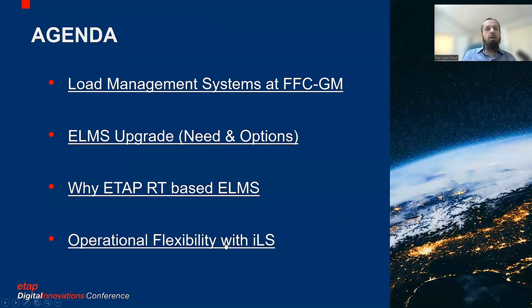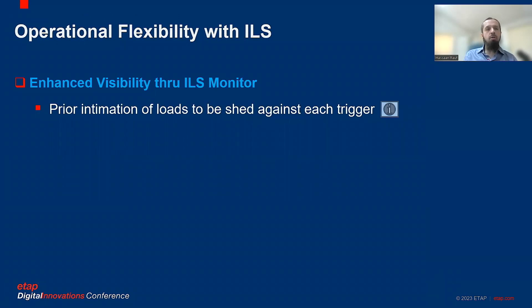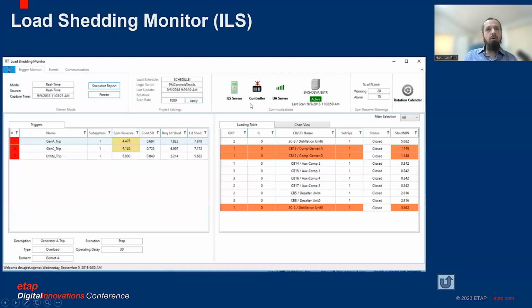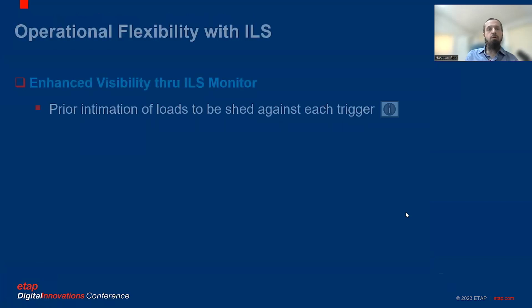So coming to the last part of my session, which is the operational flexibility which ILS brought us. First of all was enhanced visibility through the ILS monitor. We had prior intimation of the loads which will be shed against each trigger. So if I can share the ILS screenshot with you: on the left side, all the triggers of the system are listed, and on the right side is the load list which will be shed against each trigger. The highlighted loads are the loads which will be shed against a trigger. This is being dynamically updated, so based on the system conditions, the operator can see which load will be shed if this trigger condition becomes true. So this was the first requirement which was met with this system.